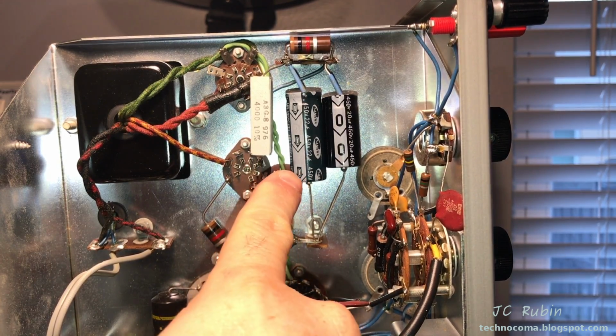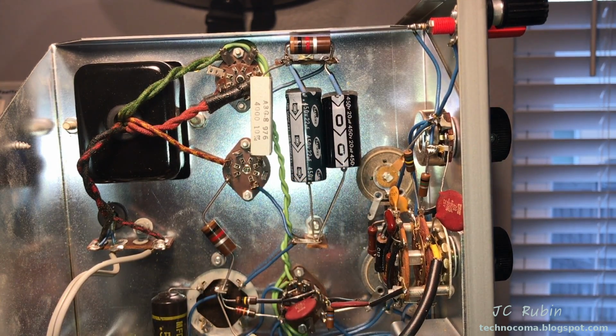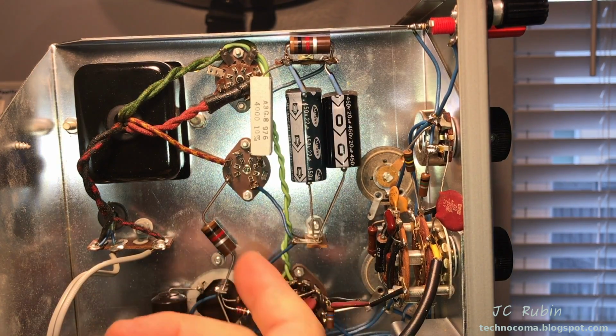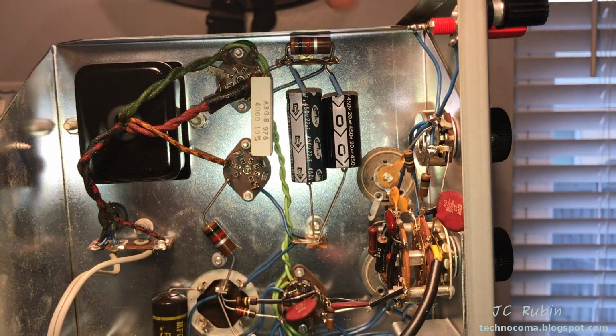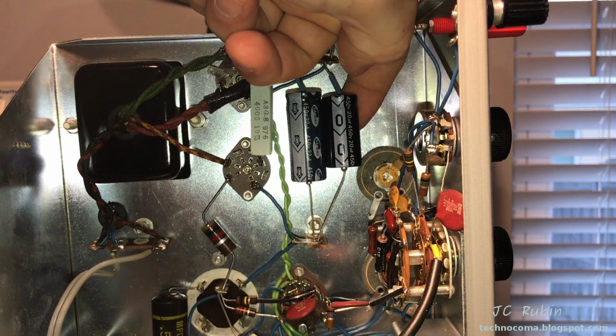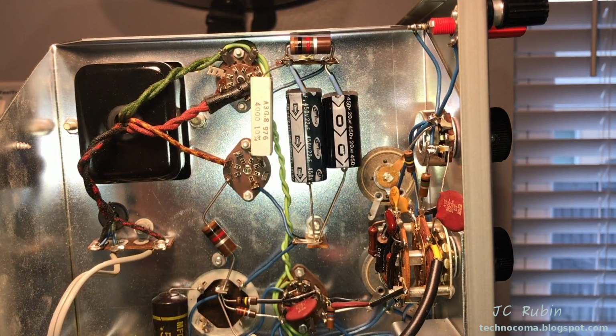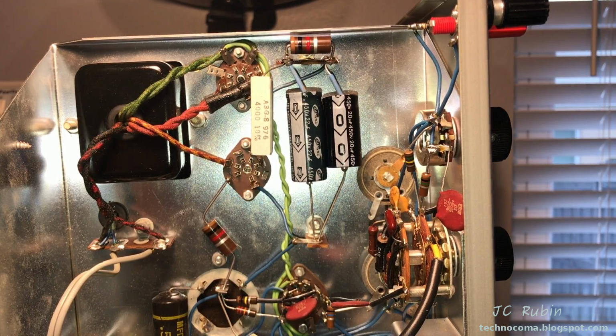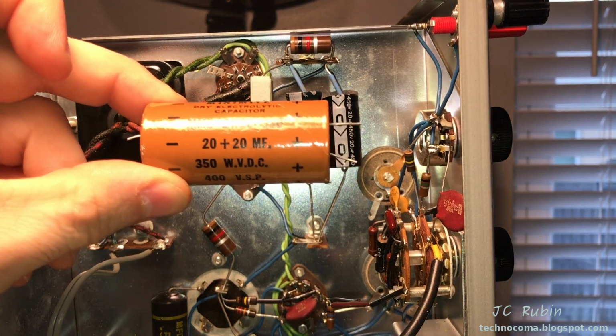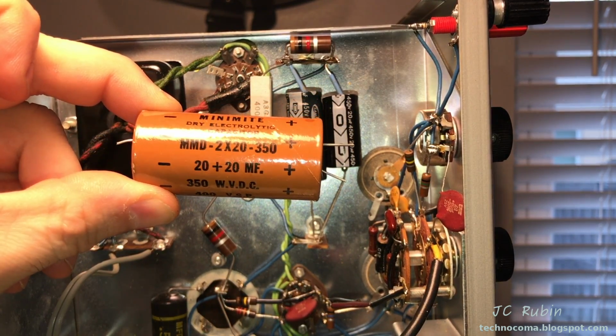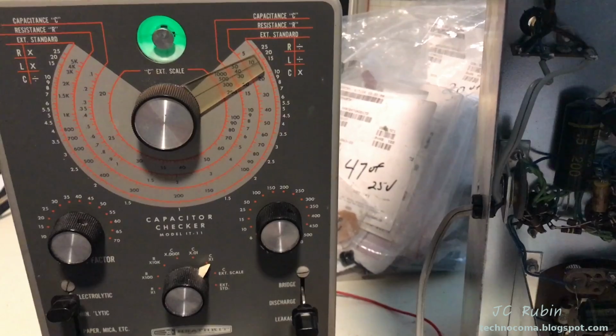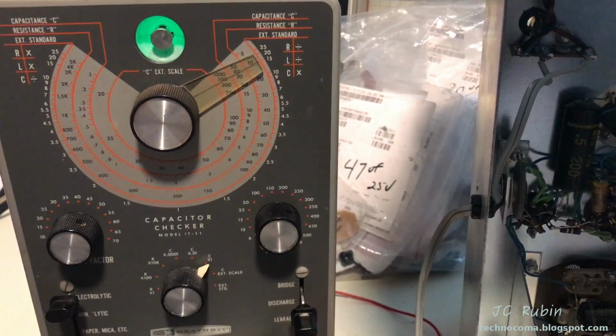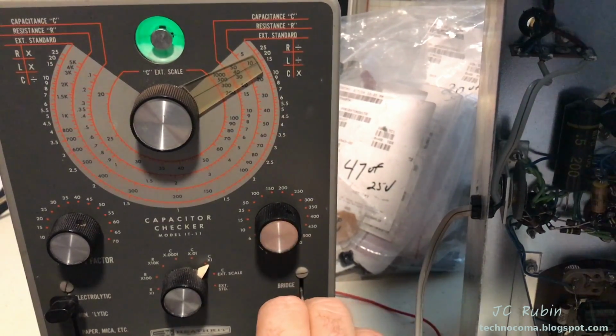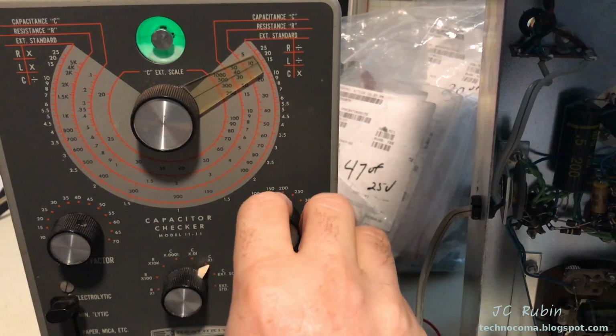I've got a 22 microfarad and a 20 microfarad. You can't tell looking at it, but these are actually floating a good way under here. It looks like they're sitting on top of it. We're going to take a look really quickly at the old one and see what the condition was if I was just to go and fire up this unit. Now I've shut the light for this event. We're going to test the first half of this capacitor now. We're on leakage.